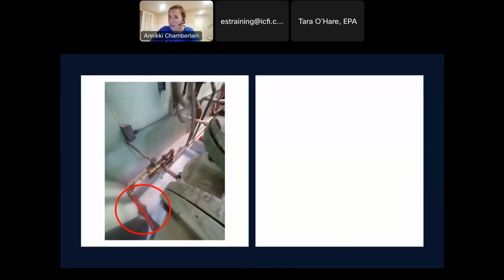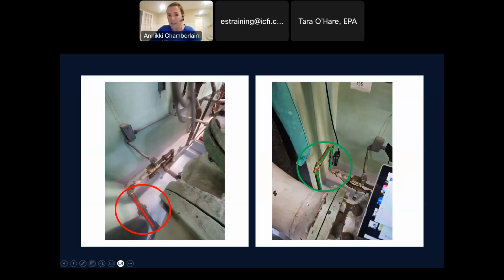So with talking straight pipe requirements, here is a blowdown system. This is the main condenser line, and then coming right off of it, it goes into the blowdown valve. So I really wanted to meter the cooling tower, but there's no way to do it because I don't have enough straight pipe where I can even get the meter clamped on. But things can be solved, so they were able to modify it. So it's coming off now. They just put in basically an upside down U, and so now my meter is clamped on right there. It's usually not very complex plumbing, especially if they have plumbers in-house. So that's one example. Basically, you're not dead in the water if you don't have it right away. You just might have to do a little pipe modification.